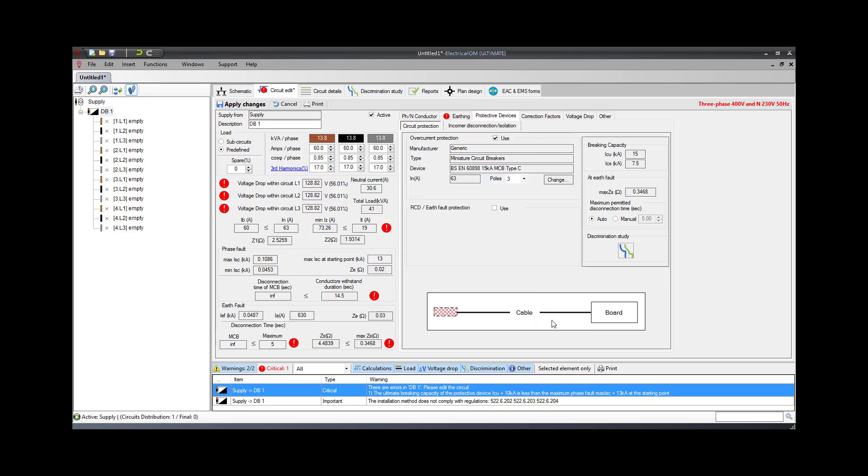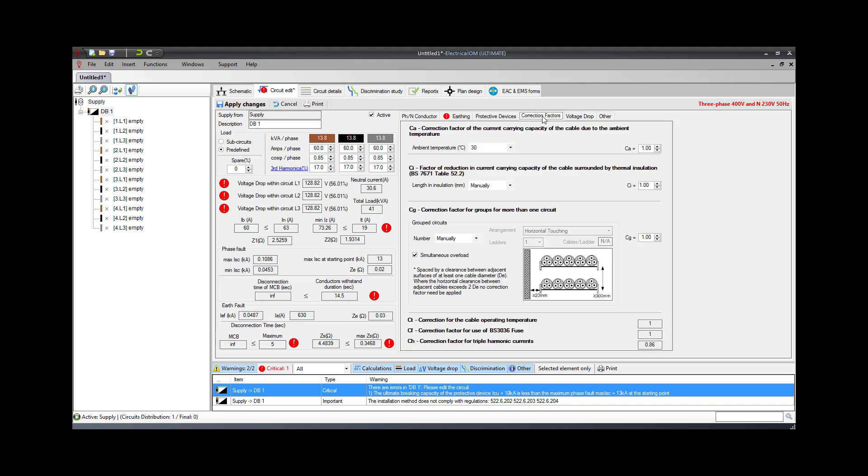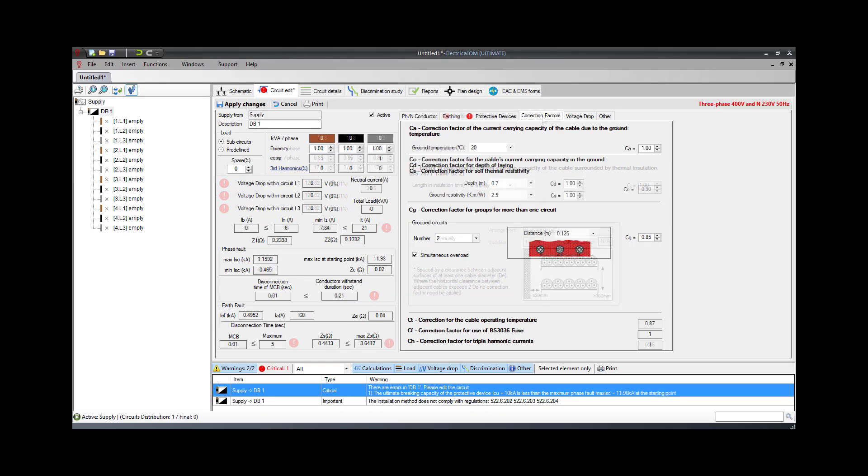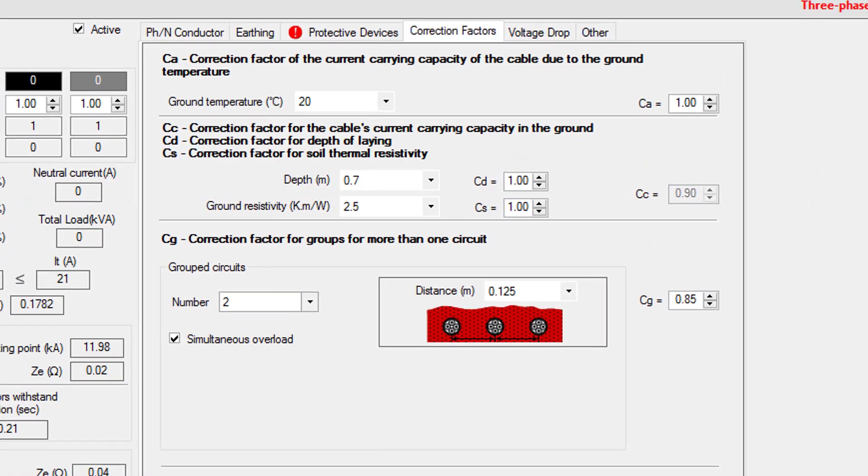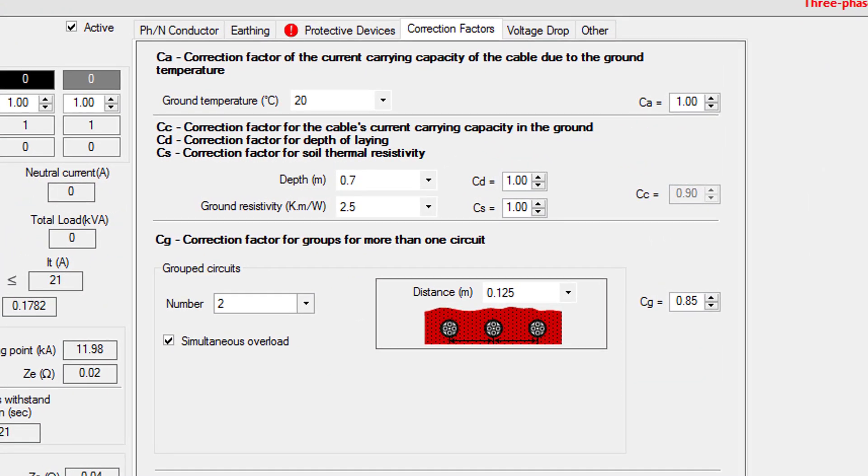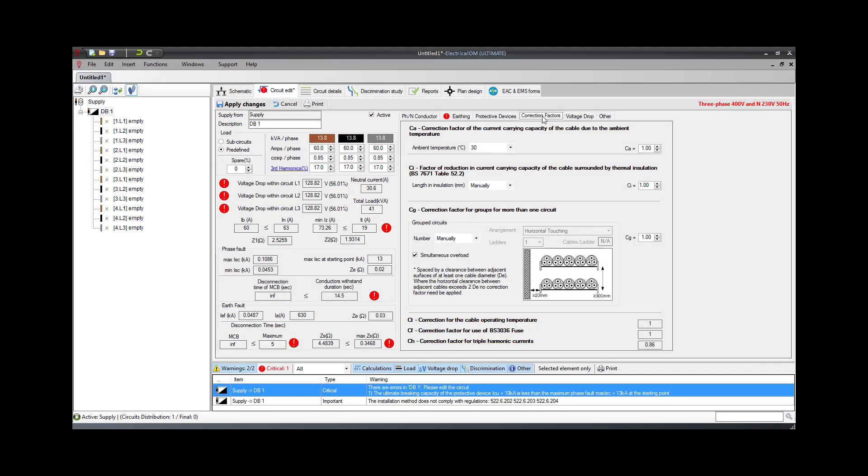During cable sizing calculations, it is important to set any correction factors based on the installation conditions. These can be the ambient temperature factor, the run-through thermal insulation factor, and the circuit grouping factor. Also, correction factors related to depth of lay and ground resistivity are available for installations in ground. Other factors are automatically calculated for compliance with BS7671.